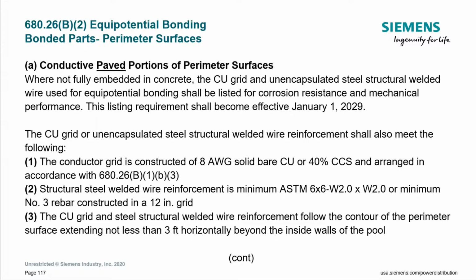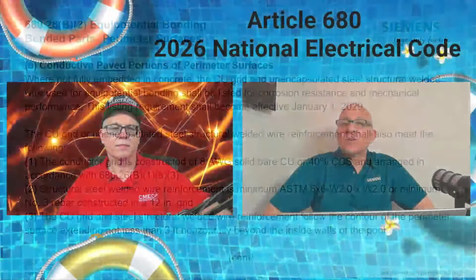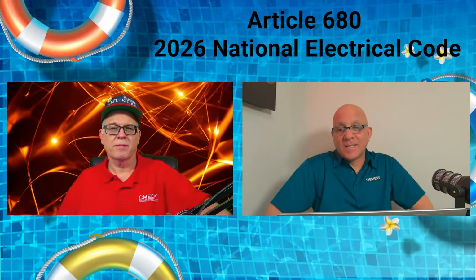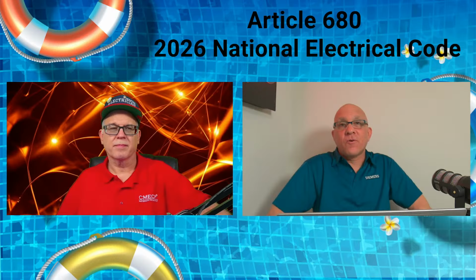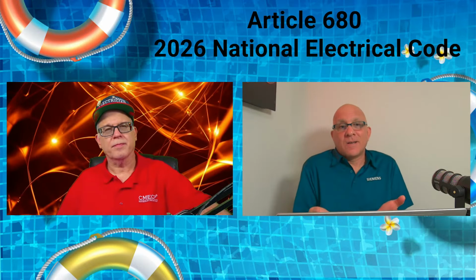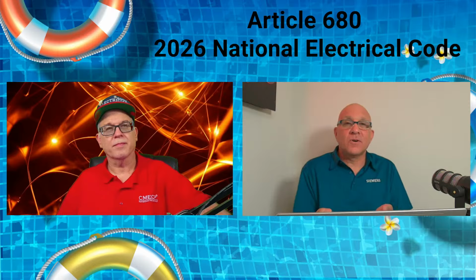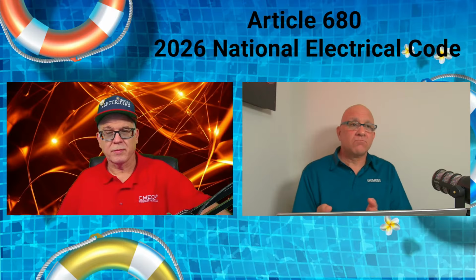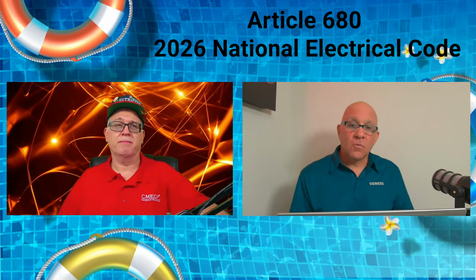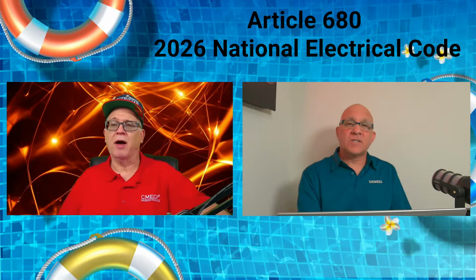Now, is it not electrical equipment? Because if it is, we can't use it if it ain't listed, remember? That's a good point. And the listing language says electrical equipment. In this application, I think you can make the argument it is electrical equipment because we're going to use it to perform an electrical function. Bonding. Well, then that would mean at this point you can't use it until the language is saying January 1st.